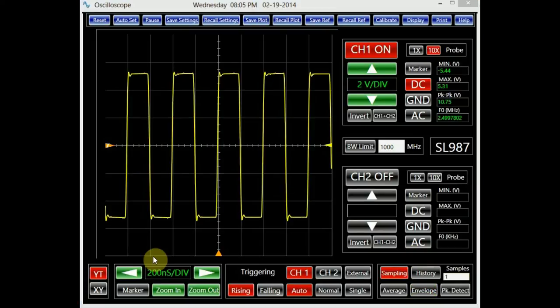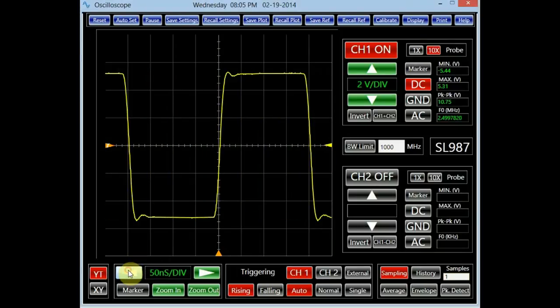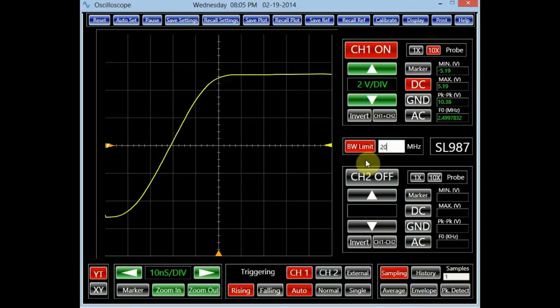The small signal 3 dB bandwidth of the oscilloscope is 1 GHz. In case the application environment contains high frequency noise and the intended signal is low frequency, the oscilloscope bandwidth can be adjusted to reduce this unwanted noise. A square wave demonstrates the effect of bandwidth reduction better than other signals. Therefore, a 5V 2.5 MHz square wave is applied to channel 1. Turning on the bandwidth limit button in the bandwidth panel reduces the bandwidth to its default value of 50 MHz. Specifying a different value in the bandwidth text box changes the bandwidth accordingly, ranging from 20 to 50 MHz. Clicking the bandwidth limit button to the off condition disables the bandwidth limit and changes the oscilloscope bandwidth back to 1 GHz.